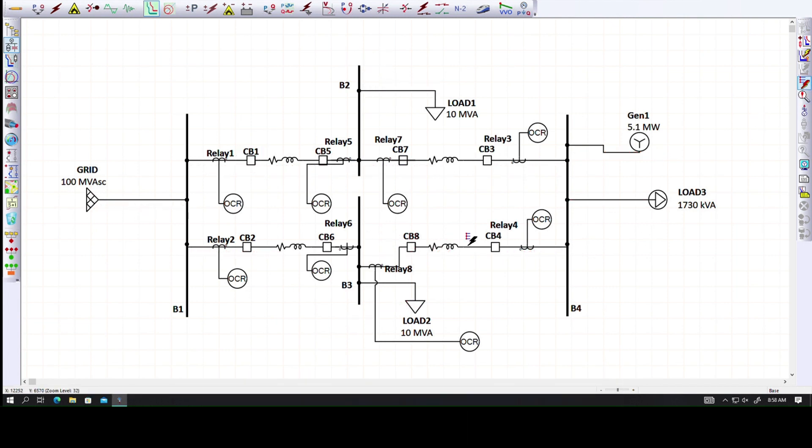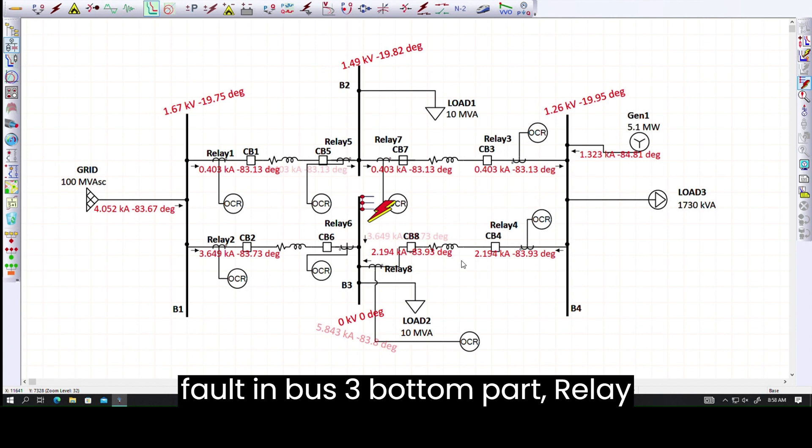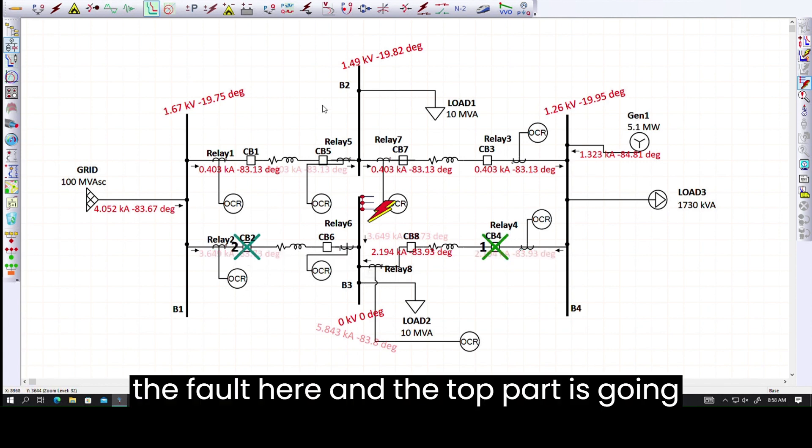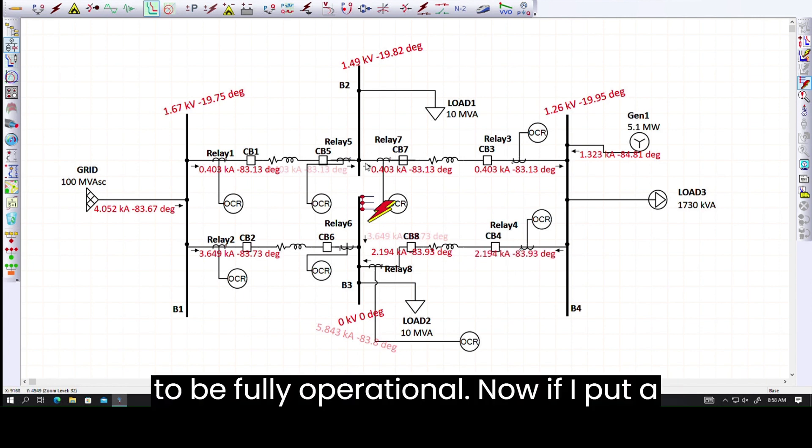Similarly, if I put a fault in bus 3, bottom part, relay 4 and relay 2 are going to trip, isolating the fault here. And the top part is going to be fully operational.